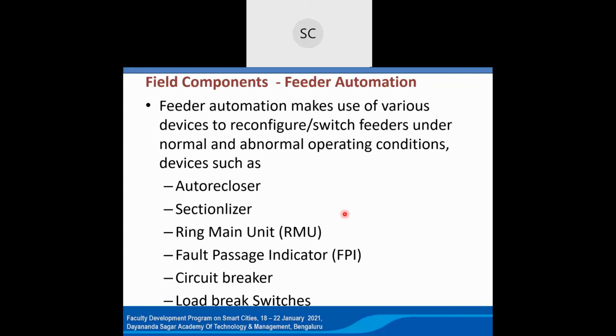This feeder automation system comprises various devices like auto reclosers, sectionalizers, ring main units, fault passage indicators, circuit breakers and load break switches. So here we will be controlling these. You know very well, in our Indian systems, many feeders are radial feeders, and down the 11 kV, data will be very, very difficult to get. Many times, whatever the lineman or that particular station engineer, assistant engineer, only knows the details. There is not much documentation. How that line is connected or not, they go by their knowledge and understanding.